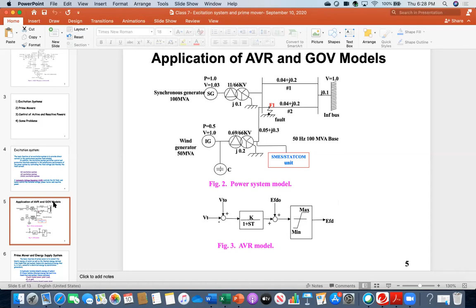That's why you see it written here: the AVR controls the DC field. And what is it controlling? It is controlling the terminal voltage, and accordingly the power factor is controlled. And if you control the power factor, you are controlling the reactive power. When the terminal voltage is low, that is equivalent to low power factor, because there is a voltage drop in the system. The system has some reactive power. That's why controlling the DC field means controlling the terminal voltage.